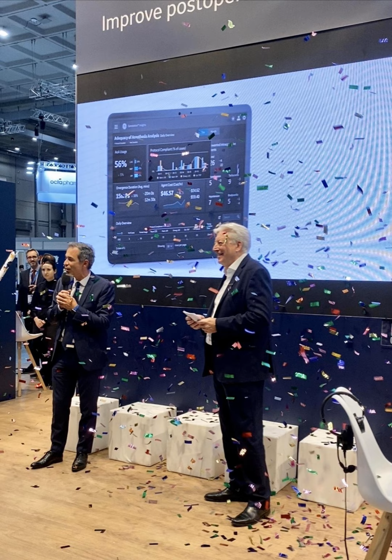Of course. So I think this is definitely something that we are embracing as well, because this is a big burden for many departments, the alarm fatigue. So through a new algorithm, we are able to reduce alarms because we are detecting when it's really relevant to trigger an alarm. And we have also some alarm notification reporting aspect into it. And it's where we are able to reduce alarm fatigue, for the patient, but also for the caregivers.